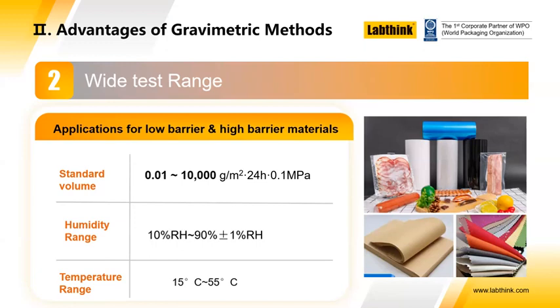In practice, if you're searching for methods which will be ultimately the most accurate or the most sensitive for measuring high barrier materials, there are other methods available which will give you another degree of sensitivity. But it's fair to say that the range offered by ASTM E96 is one of its major attractions, in that you can test a wide variety of materials, not only variety due to their physical makeup, but also variety due to their barrier properties. And the humidity range achievable is between 10 and 90% plus or minus 1%, and a temperature range of around 15 or 20 Celsius up to 55.